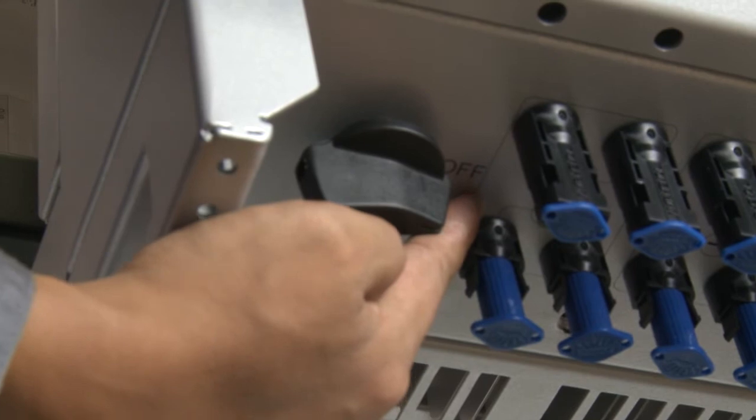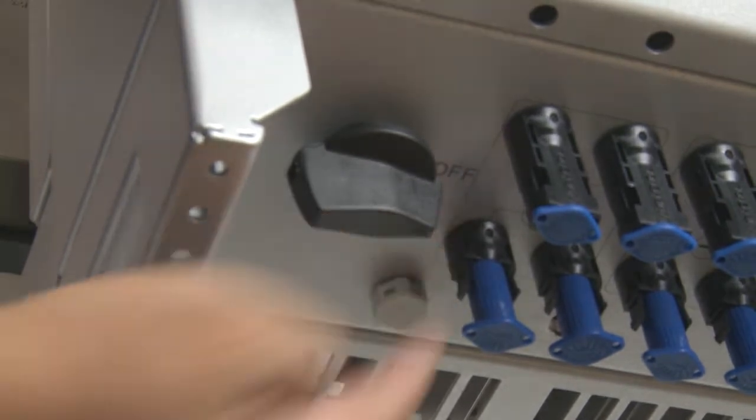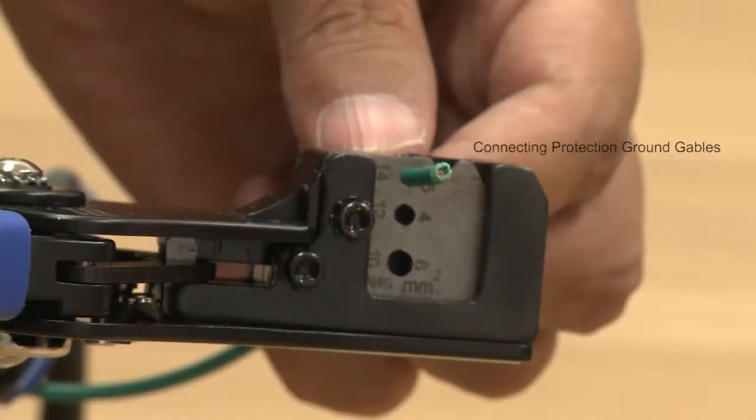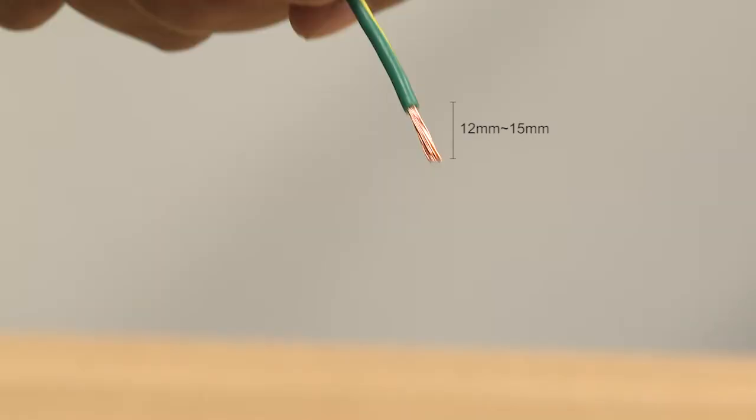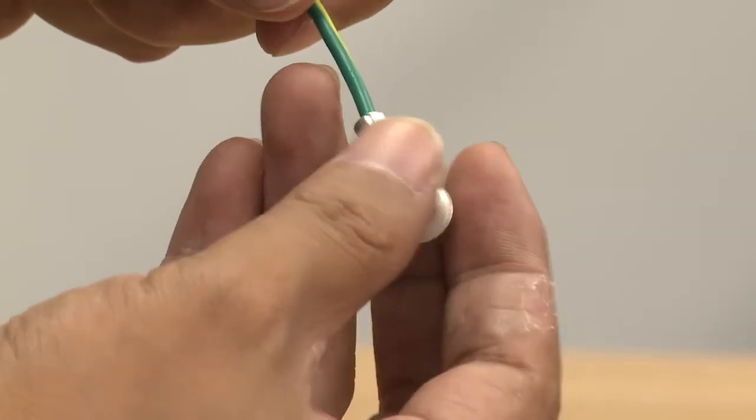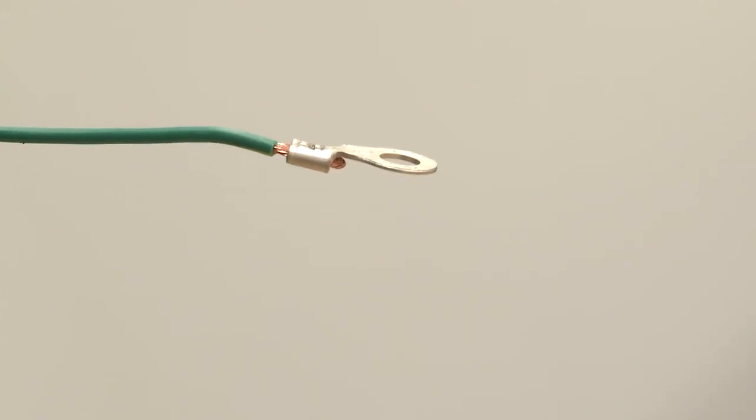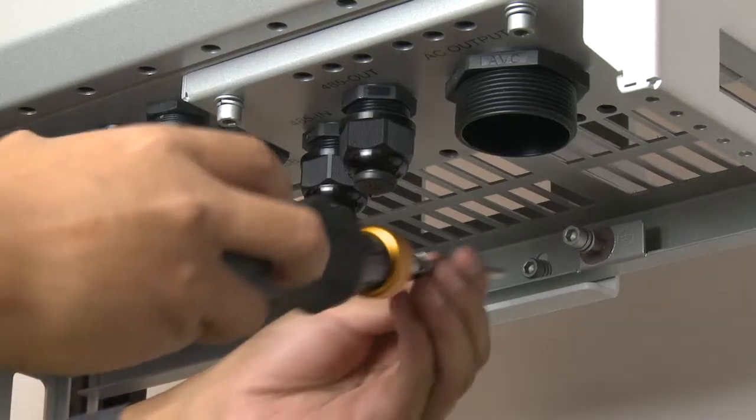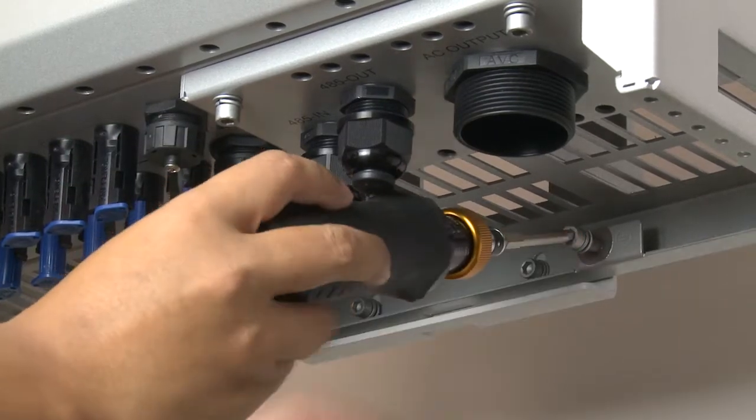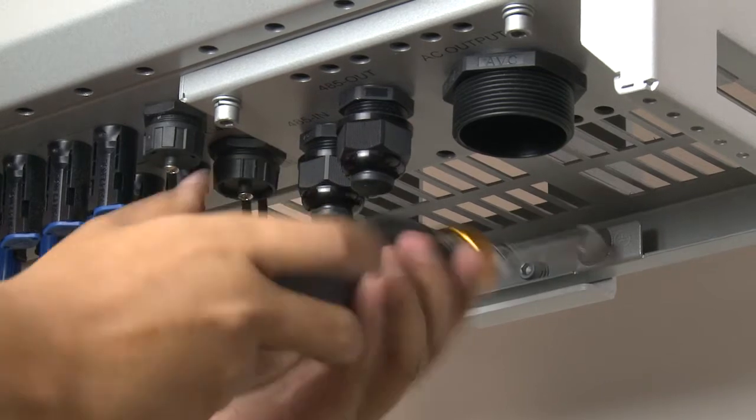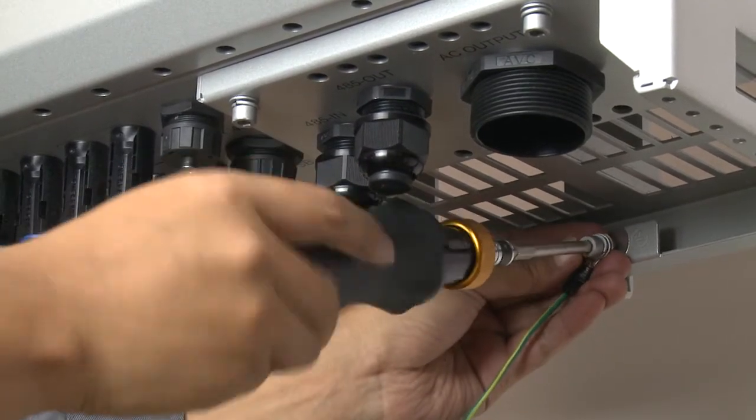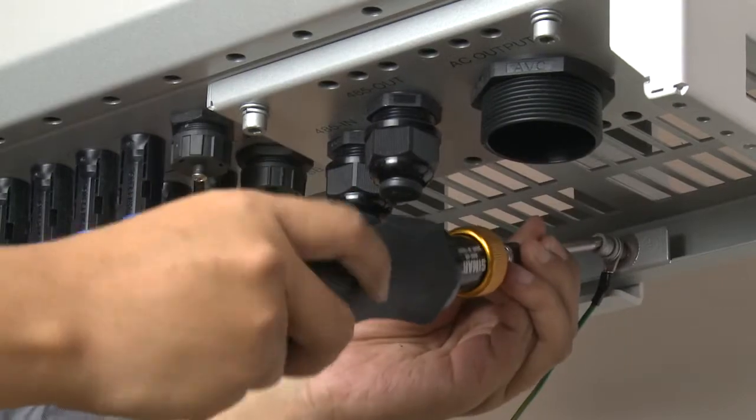Ensure that the DC switch is set to OFF. Remove an appropriate length of the insulation layer from the yellow-green earth wire using the wire strippers. Crimp the earth wire into the OT terminals using the crimping pliers. Remove the cross screw on the inverter with the Phillips screwdriver. Route the screws through the OT terminal and tighten it firmly with the Phillips screwdriver.